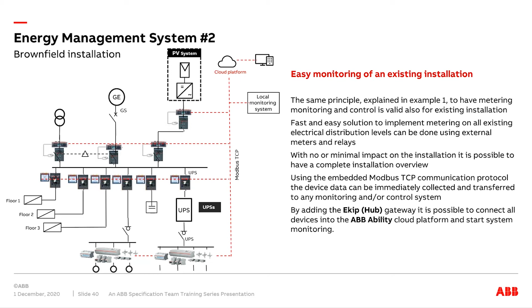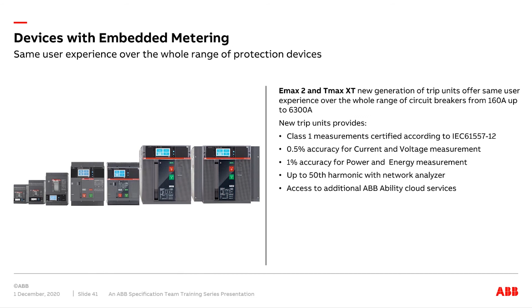As I touched on earlier, devices with embedded metering are now the driving force behind a lot of metering devices in the market today. It's not just standalone metering, it's devices that give you a lot of data embedded to it. Focusing on Emax2 and Tmax XT, a range of ABB circuit protective devices, you can see from the figures there very accurate class 1 measurement: 0.5% accuracy on current and voltage, 1% accuracy on power and energy management. We can also introduce other performance factors such as harmonic analysis, all with the ability to centralize this in the ABB Ability Cloud service.